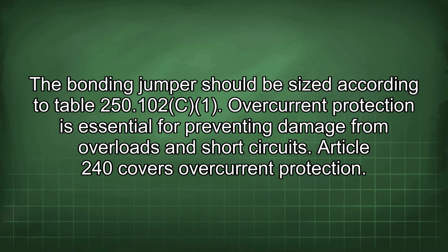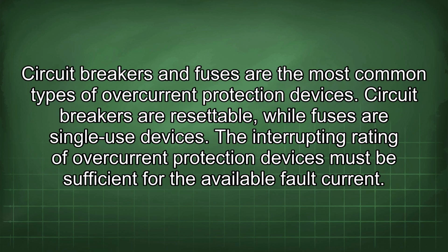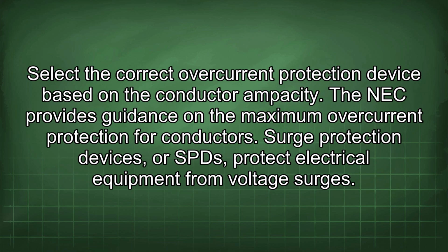Article 240 covers overcurrent protection. Circuit breakers and fuses are the most common types of overcurrent protection devices. Circuit breakers are resettable, while fuses are single-use devices. The interrupting rating of overcurrent protection devices must be sufficient for the available fault current. Select the correct overcurrent protection device based on the conductor ampacity. The NEC provides guidance on the maximum overcurrent protection for conductors.